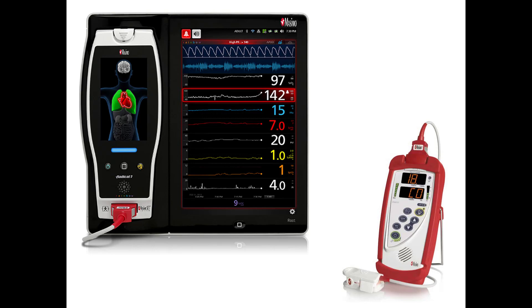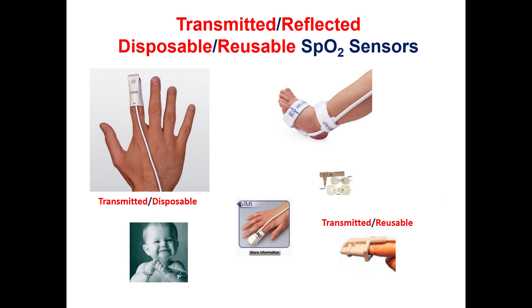We can classify the pulse oximeter depending on how many wavelengths are used. We have now some images for reusable and disposable pulse SpO2 sensors. The transmitted type disposable sensor is used only a single time and then discarded. This disposable transmitted SpO2 sensor is used on the finger.